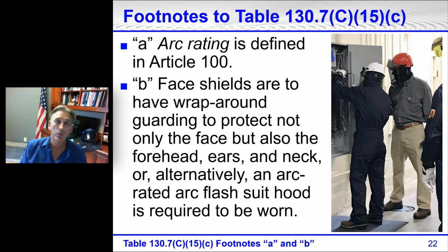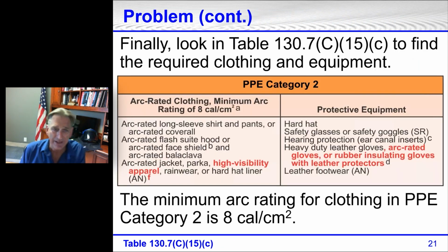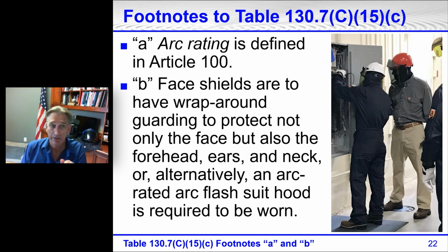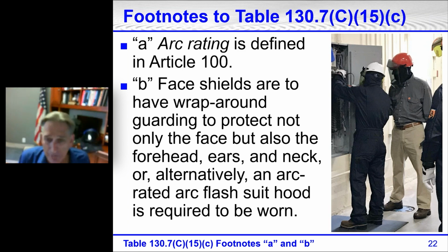There's some footnotes with that table. Footnote A, in fact, let's go back. Footnote A is at that top line after a minimum arc rating of 8 calories per square centimeter, and then going on down, we've got arc rated arc flash suit hood or arc rated face shield, and so this is the first footnote, the arc rating, and that is defined in Article 100. And B is face shields are to have a wraparound guarding to protect not only the face, but also the forehead, ears, and neck, or alternatively, we could use an arc flash suit hood instead of the arc rated face shield and possibly the arc rated balaclava.